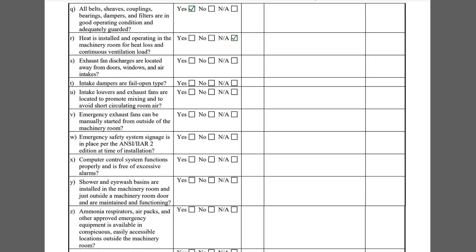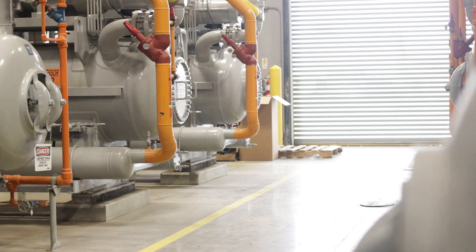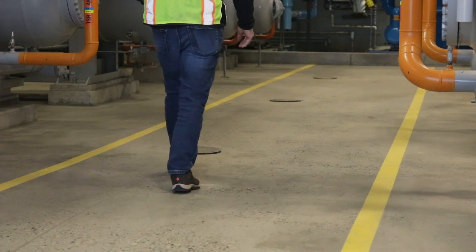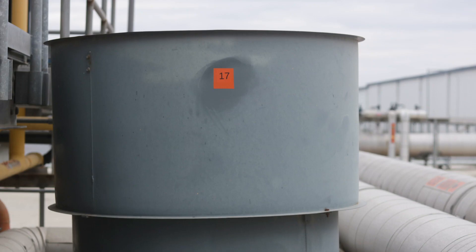Item R asks if heat is installed and operating in the machinery room for heat loss and continuous ventilation load. Since this machinery room is located in a moderate California climate, no additional heat load is required and the question can be answered NA. Item S asks if the exhaust fan discharges are located away from doors, windows, and air intakes. This fan satisfies this requirement.